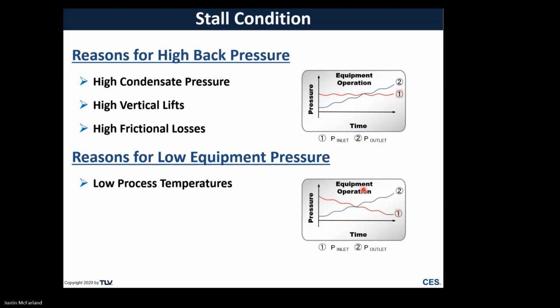Now, that probably all makes sense, but low equipment pressure probably is a little bit more unusual to people. So the biggest reason that we see is low process temperatures. Great analogy for this is think about a hot water system. So if you have a hot water system at your house, it's probably electrical, but let's just say it's heated by steam. And knowing that, the water temperature when it sets is probably not going to be any more than 150 Fahrenheit or so, then I'm just going to guess that the steam temperature that we need in order to get water to 150 has got to be more than 150 Fahrenheit. Does it need to be 300 degrees Fahrenheit? Does it need to be 200 degrees Fahrenheit? There's no wrong answer to that.